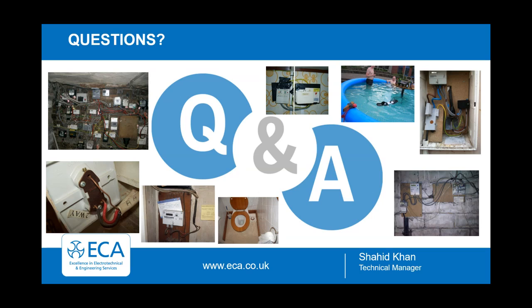Was that for me, Mike? For you or Gary, or just a discussion point? Well, to be honest, if all the Zs values are coming out okay, you've done your inspections, everything looks fine, everything complies in terms of automatic disconnection, then just because we've got old wiring colours and old gear, if it's not unsafe, do we have to upgrade it?